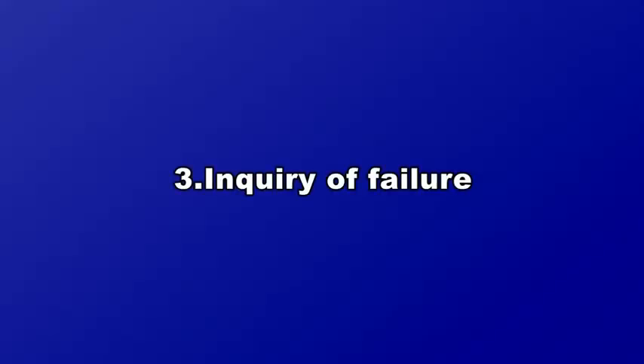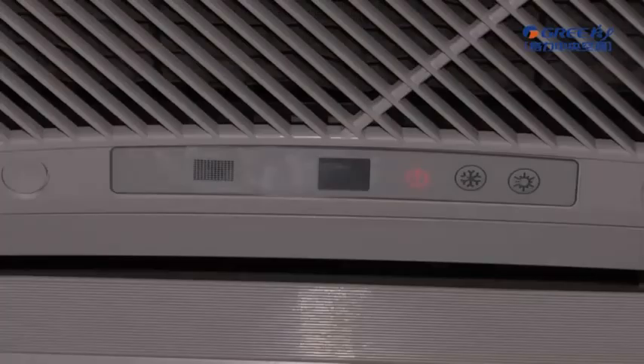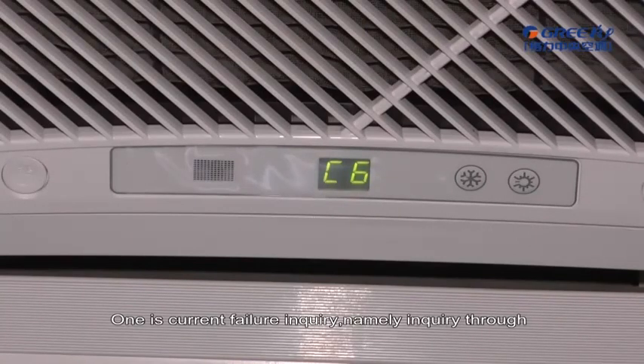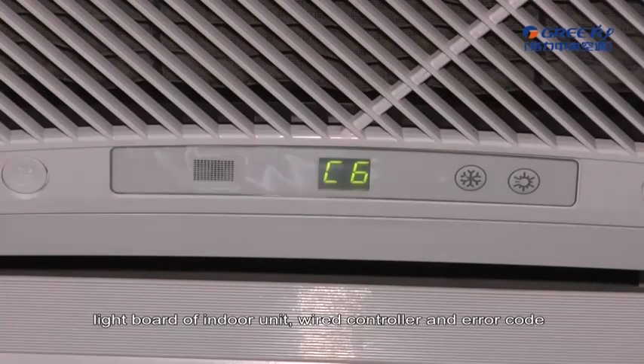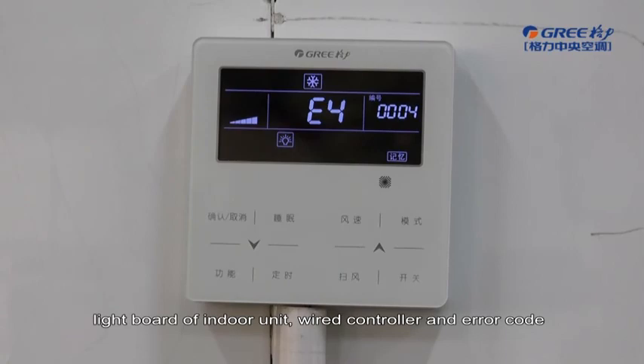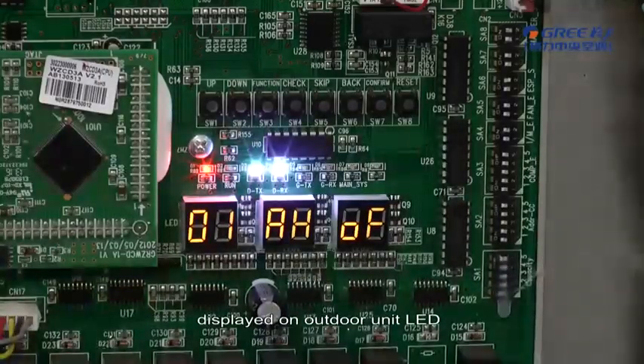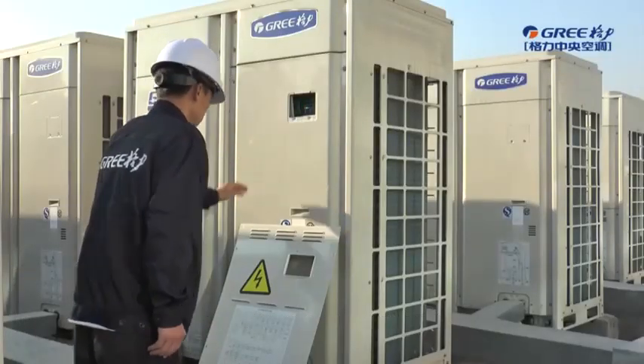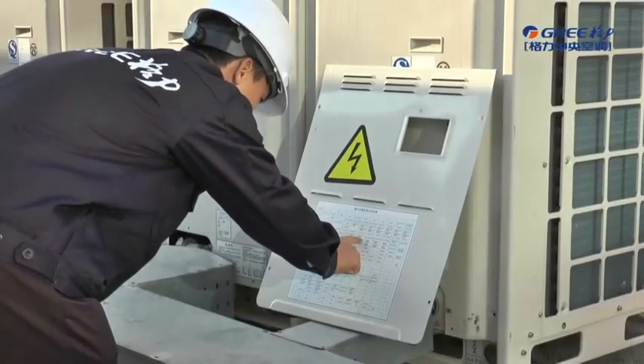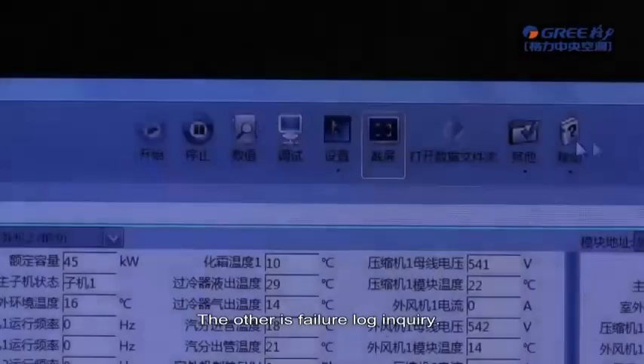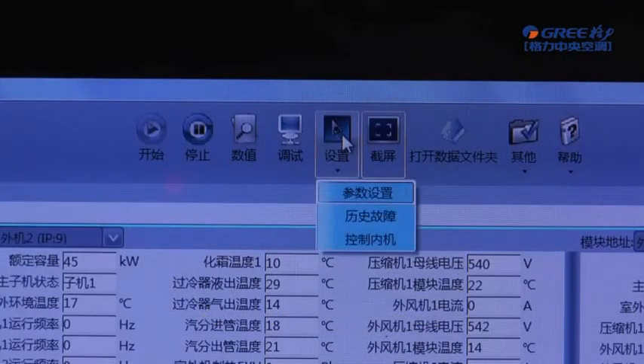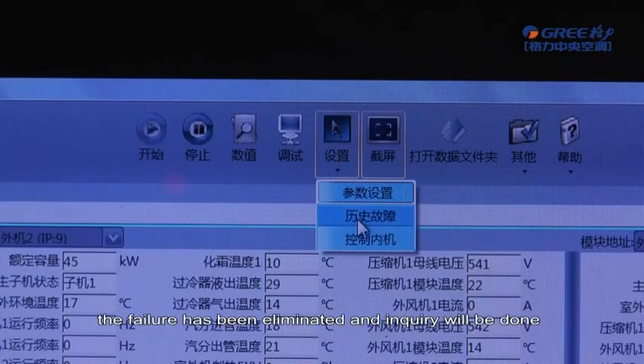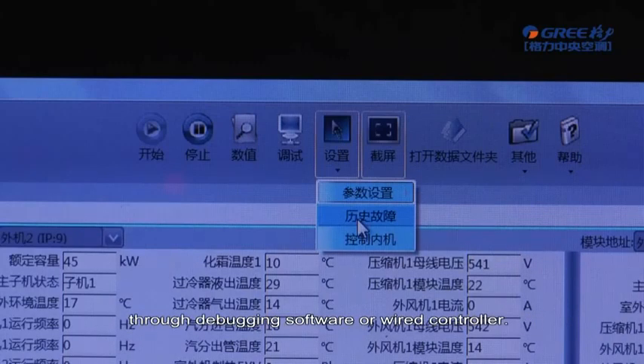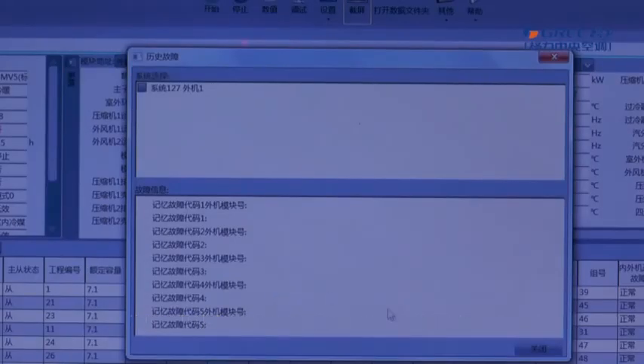3. Inquiry of failure. There are two methods of failure inquiry. One is current failure inquiry, namely inquiry through light board of indoor unit, wired controller, and error code displayed on outdoor unit's LED. The other is failure log inquiry. In this case, the failure has been eliminated and inquiry will be done through debugging software or wired controller.